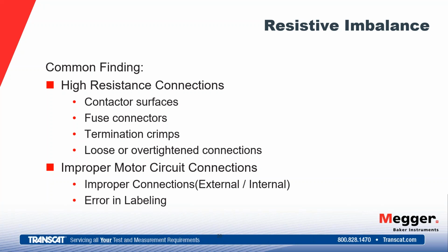Could be improper motor circuit connections. If you're testing at the motor, then it's suspected that there are improper connections internally to that motor. It may be just an error in labeling. So you've got the 12 connections coming out and the lines are mislabeled and you've got issues there. So you can find connection issues internal to that motor.